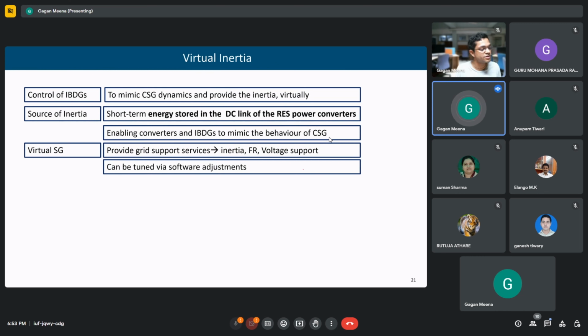What is the source of the inertia in these generators? It is the short-term energy stored in the DC link capacitor, so the DC link of these converters is the source of the energy. For the conventional generator, the source of energy is the kinetic energy stored as inertia, which is converted into electrical energy.